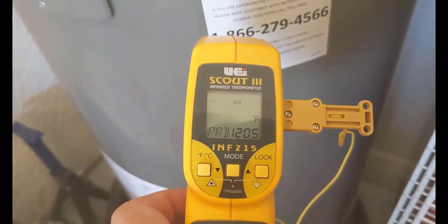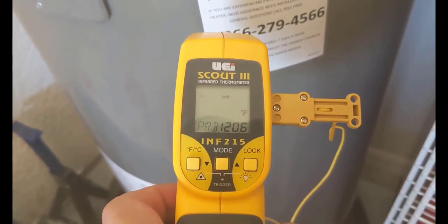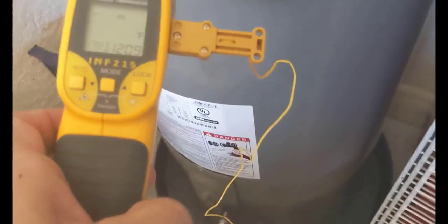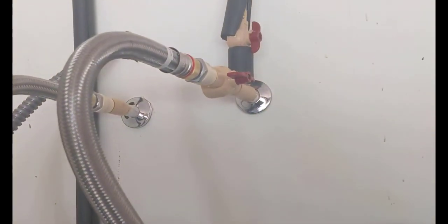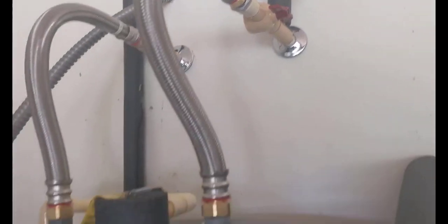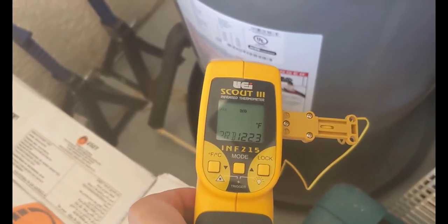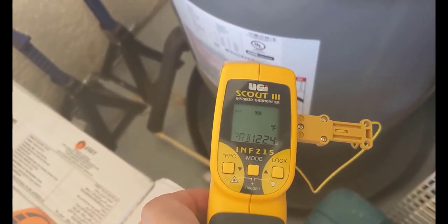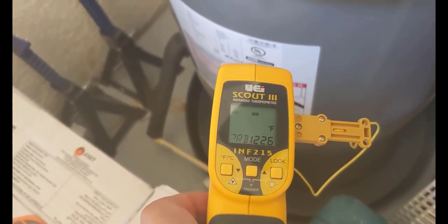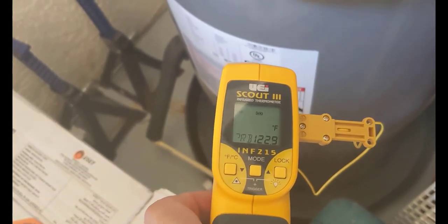So there we go folks, we got 120 degrees coming back from the heat recovery unit, 120 degrees and climbing. So this is showing you that it's taking the water from here at about 90 degrees, sending it over to the heat recovery and coming back from the bottom which is where it's tapped into at 122 degrees and climbing.